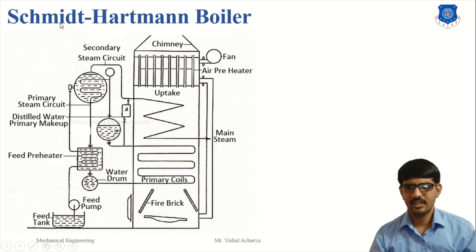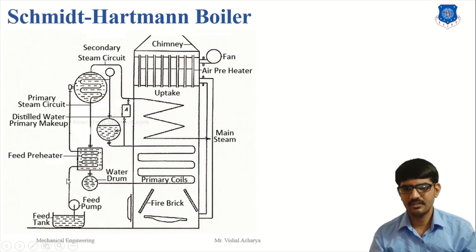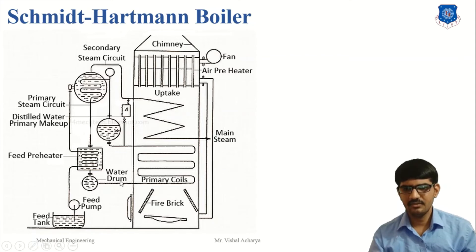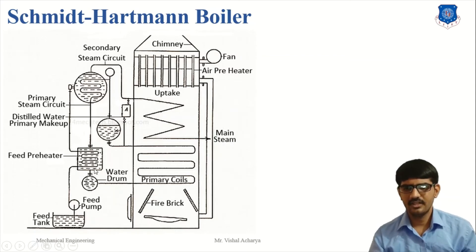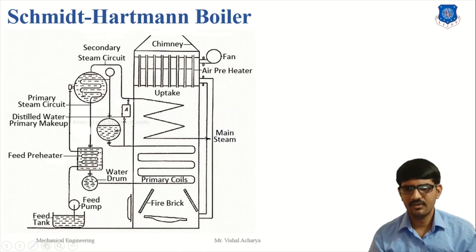Next is the Schmidt-Hartmann boiler. The main working principle involves two circuits. The first is the primary circuit and the second is the secondary circuit. In the primary circuit, distilled water is used, and in the secondary circuit, regular water is used. In the primary circuit, the pressure of the steam is above 100 bar, and in the secondary circuit, the pressure is only 50 to 60 bar.